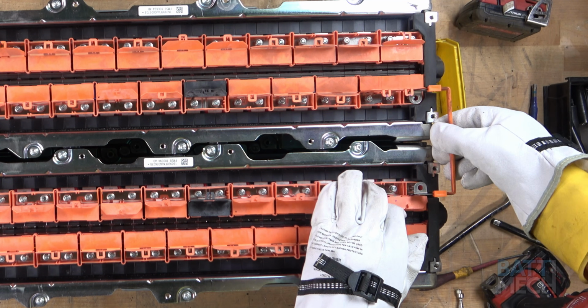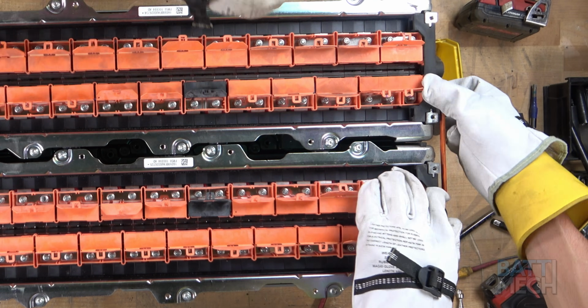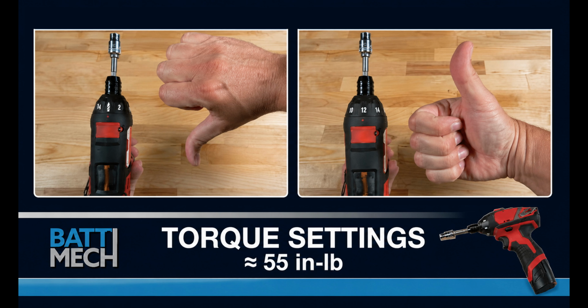During this stage, you'll need to reattach the wire bridge as well, then tighten the nuts to the terminals. Don't forget, be sure your torque wrench is set to about 55 inch-pounds. If you don't follow these torque settings, you are likely to damage the terminals on the batteries and will void your warranty. Never use max drill settings and never use an impact wrench.